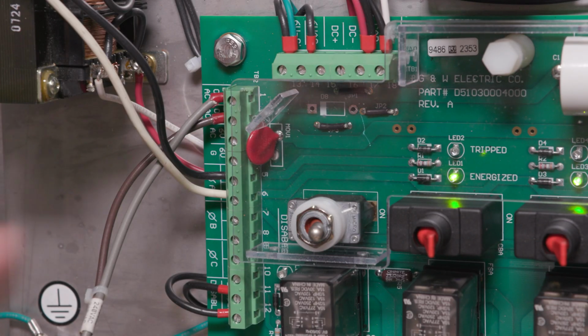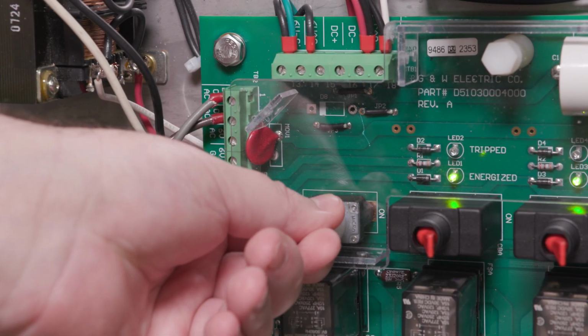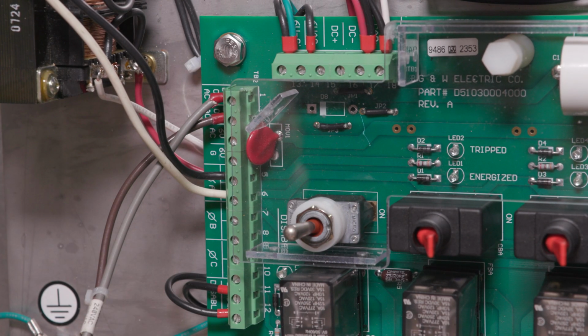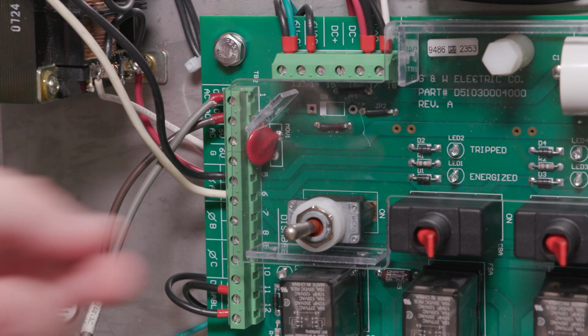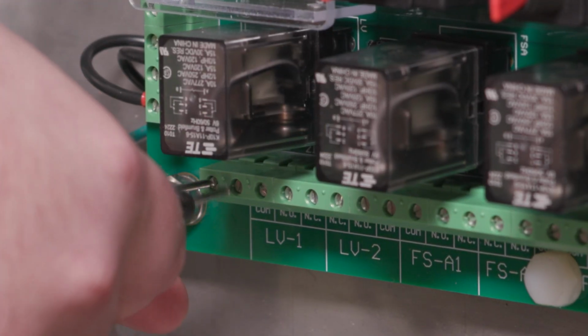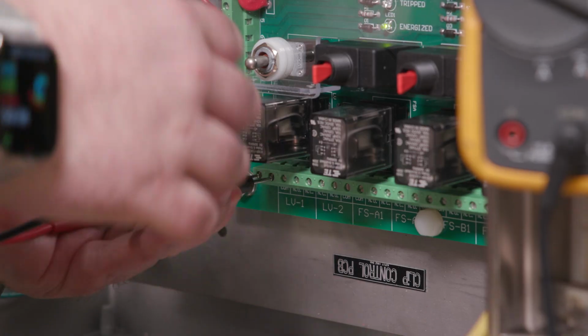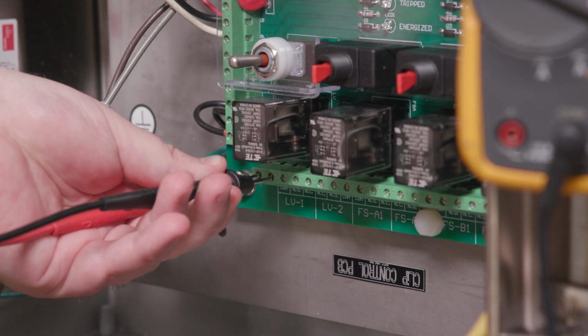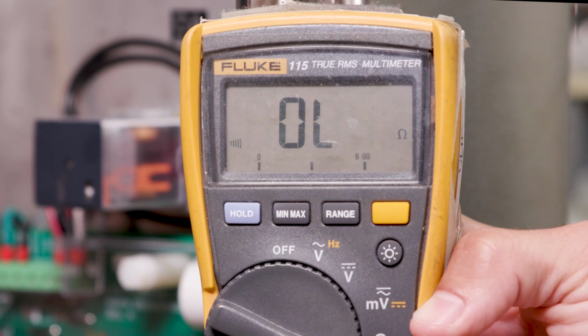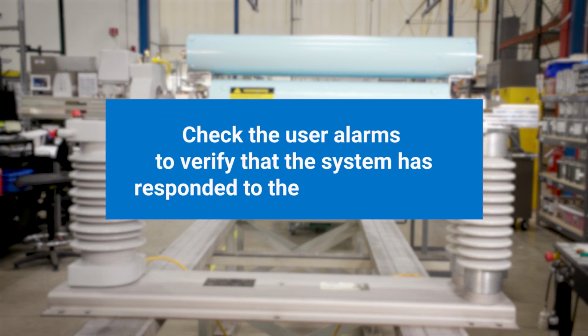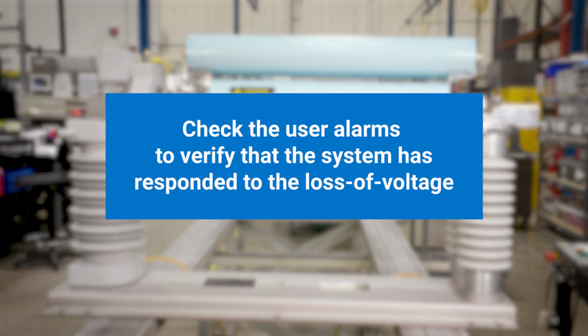Now de-energize and re-energize the control power supply. Do this by turning the circuit breaker off and on and ensure the lights act accordingly. And verify the proper operation of the loss of voltage relay and its contacts at the terminal strip. Also verify the contacts toggle from open to close. Next, check your user alarms to verify that the system has responded to the loss of voltage.